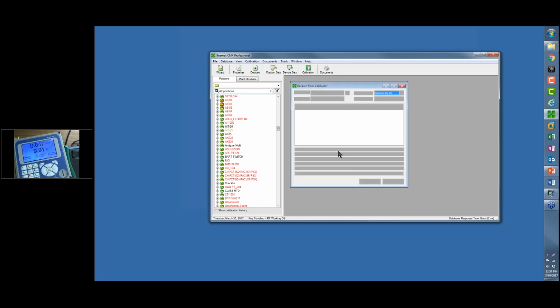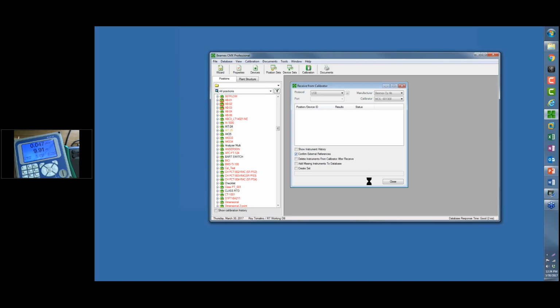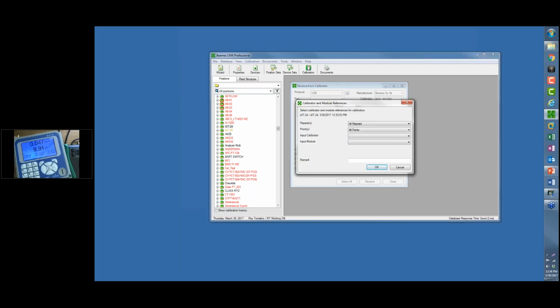Calibration, receive. I want to confirm external references because I was using a pH standard that the software or the calibrator didn't know about. So I'll bring this one over and receive it. I know you guys are thinking, please put it back on the screen. I know, but I'm back. Before I did this test, I put in these buffer solutions in the software as a calibrator.